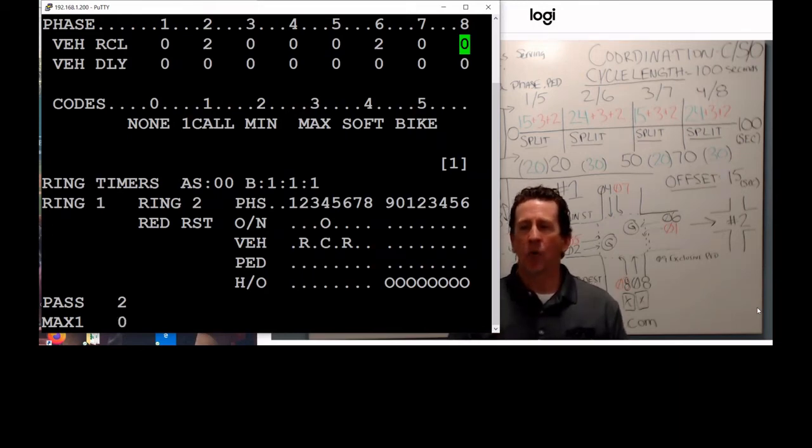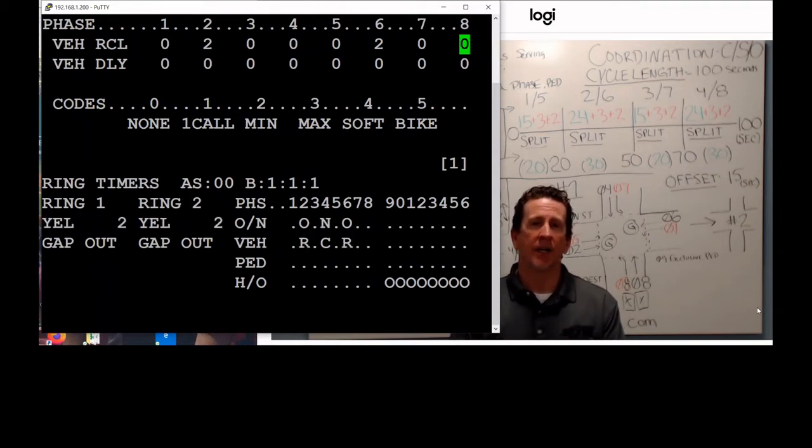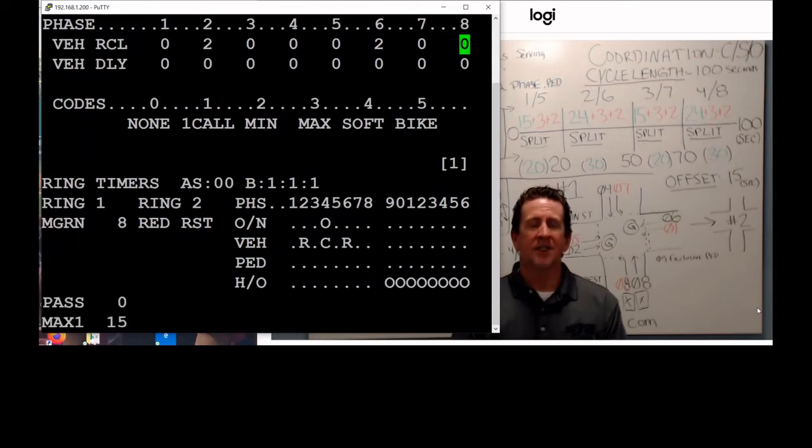It allows you to get more troubleshooting logs, which we'll go into later. So when people call me up and they have a problem, I say, let's go to the alarm menu. And in there, we can generate frame faults, which tells us if BIUs are bad. A BIU is a bus interface unit. So that takes all the input, output, and voltage data, and sends that back to the controller and the MMU.